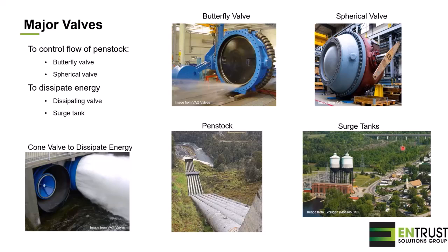Here we have an embedded penstock underground that we cannot see, but we have a surge tank. So if we shut down the turbine very rapidly, then the extra water, the extra pressure, will go into the surge tank and dissipate there.